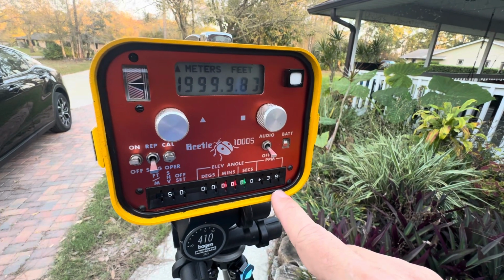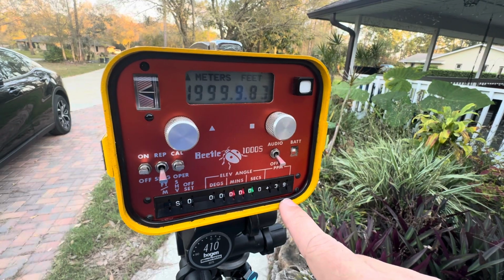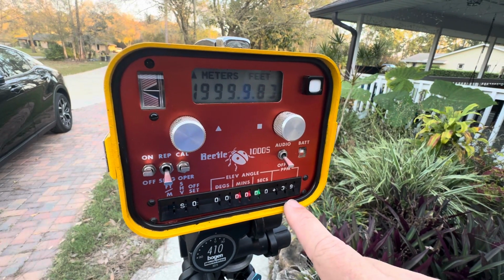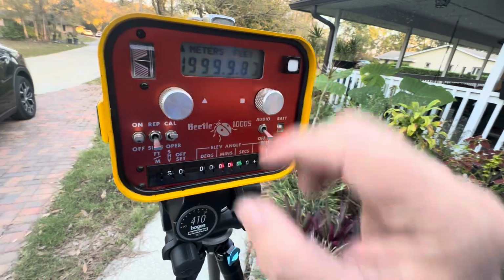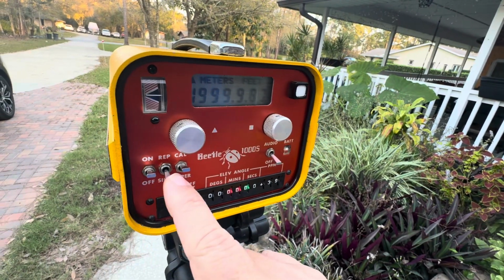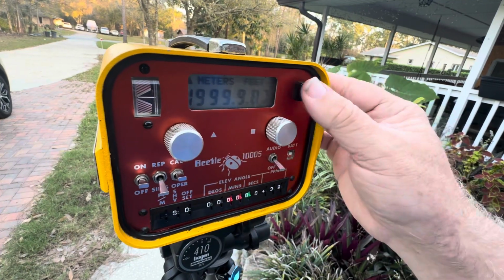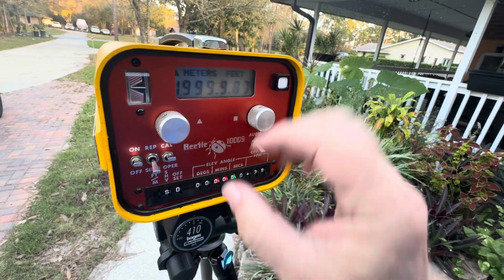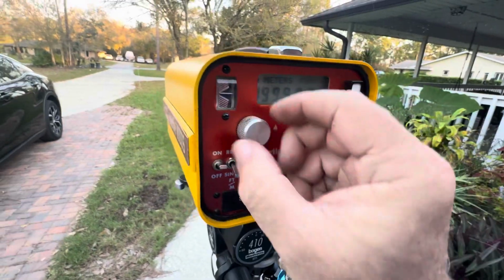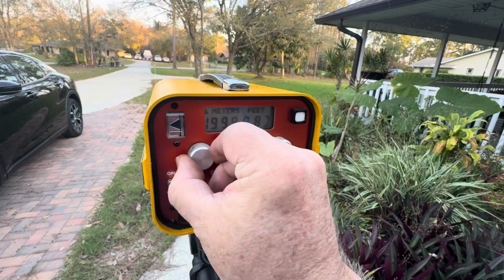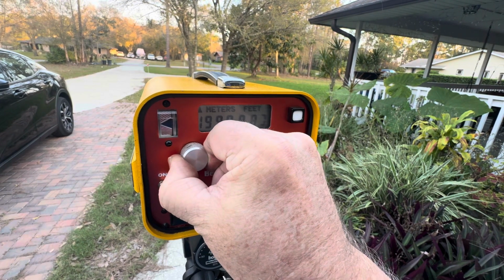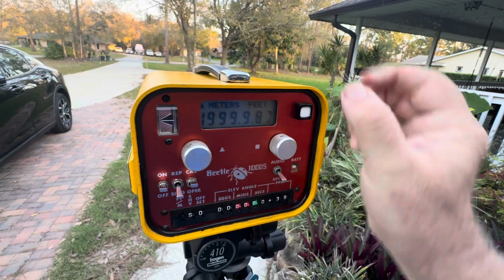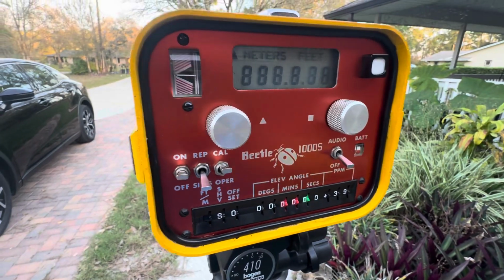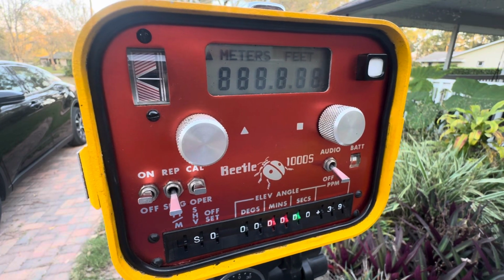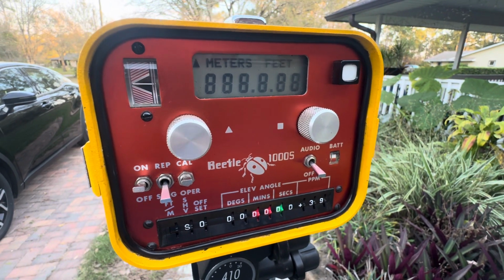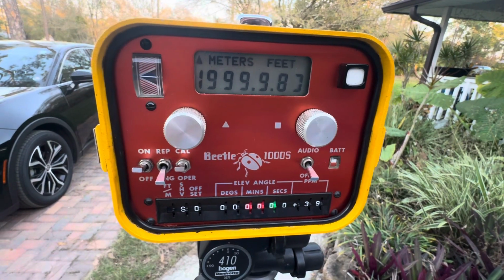And that is actually the current one for 75 degrees and 30.15 inches of mercury. Set it on 39. What you would do is let it warm up for a minute or so, and you put it on single operation, and this is the button to trigger a reading. You'd put it in calibration, and this is the calibration sensitivity on this side. You can see as I move it in here. So you put it right at the point of that arrowhead, and you fire off a calibration. And you're trying to get as close to 2,000 as you can.